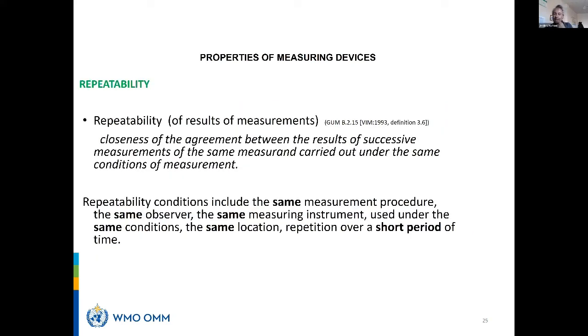Two very difficult terms - I've been in metrology for about 30 years and I still have difficulty with one or the other, so just keep them in mind. Repeatability: I'll just read it. It's the closeness of agreement between results of successive measurements of the same measurand carried out under the same conditions. This is done when you do a calibration, or when you repeat measurements the same way - same observer, same measuring system, same condition, same location, a short period of time, and the same measurement procedure.